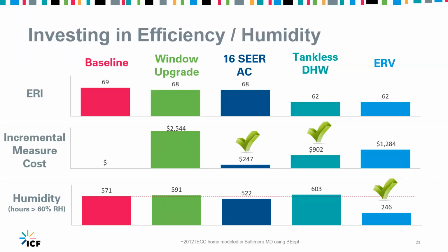But then if we look at these first three measures, you don't really see much of a change at all in terms of their impact on the humidity in the home. But the ERV has a huge impact on humidity in the home. So after I put these together, I thought I should mention that I'm not an ERV salesman. I don't have any stock in them. It just happened to be a good way to illustrate humidity impacts.